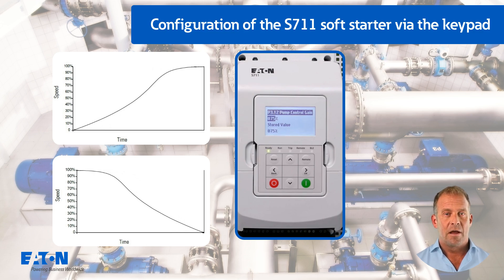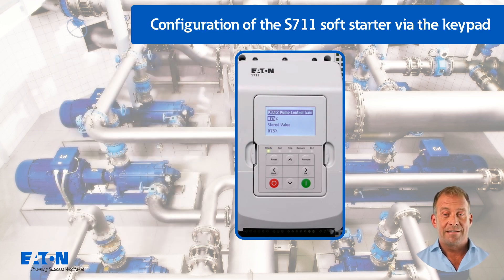P3.12 can be used to determine how much the soft starter adjusts future starts and stops based on the information from the previous start. The gain setting influences both the start and stop behaviour.